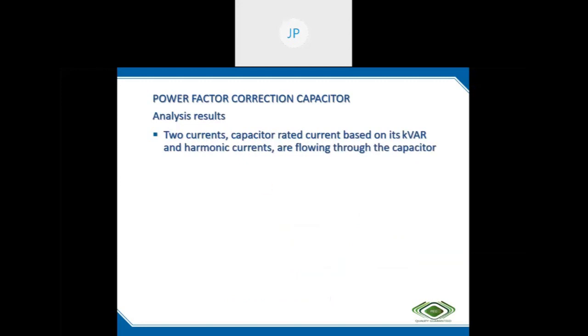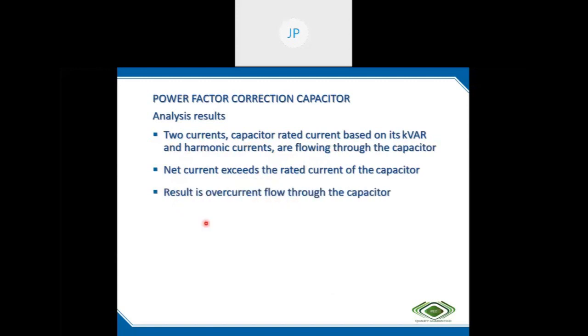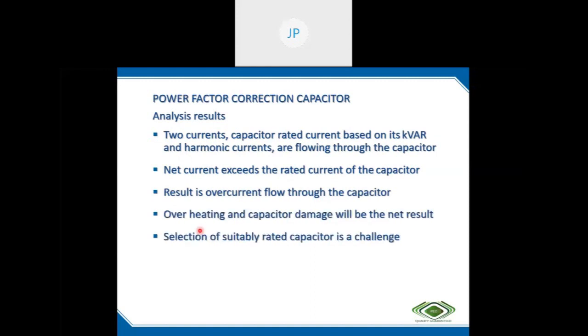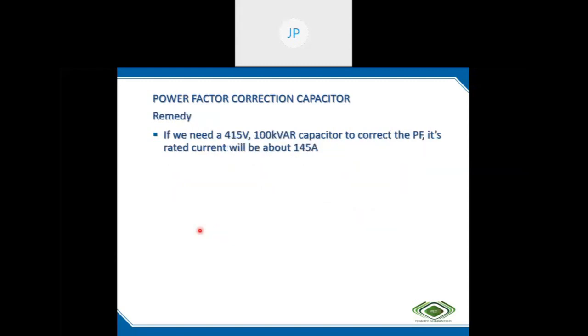So the observation is, we can see the capacitor current and harmonic current flowing through the same capacitor. The net current exceeds the rated current. The result is overheating and capacitor damage. Here, how to select a suitably rated capacitor? That is a little complicated, but we can explain here. If we need a 415 volt 100 kVAr capacitor to correct the power factor, this 100 kVAr will draw around 145 amps.